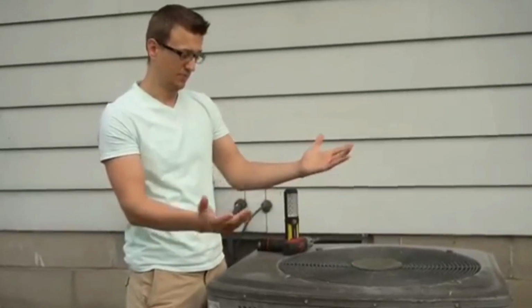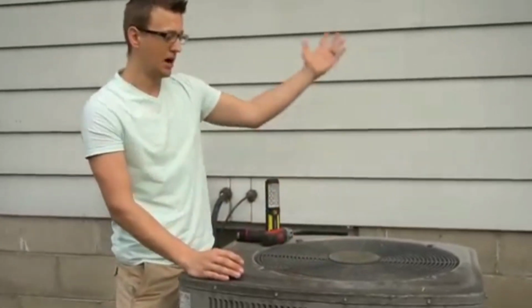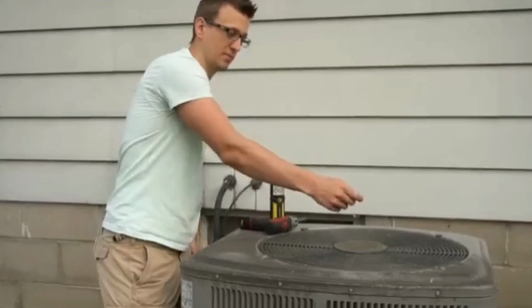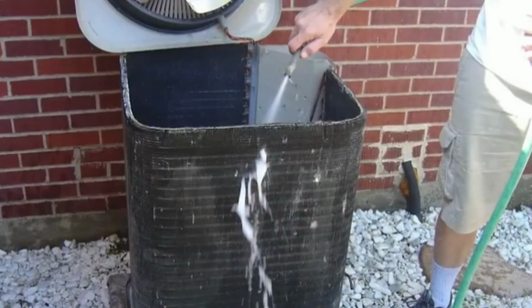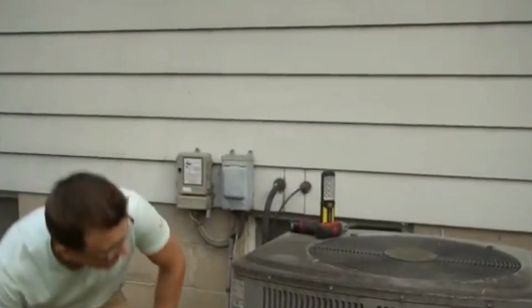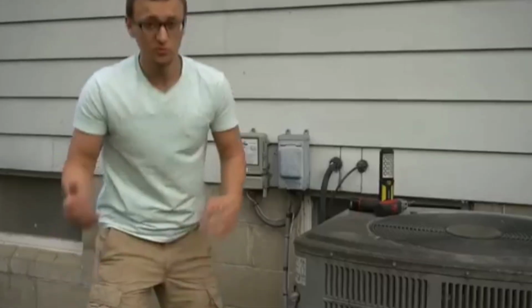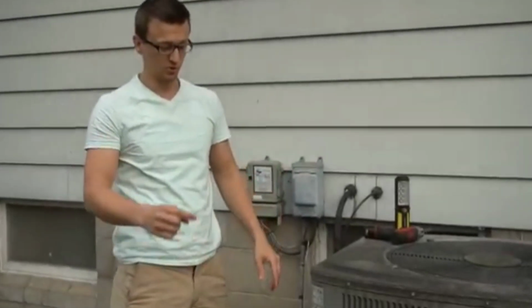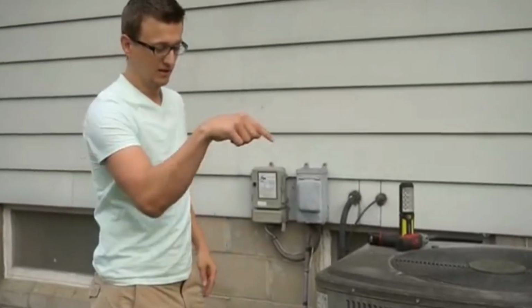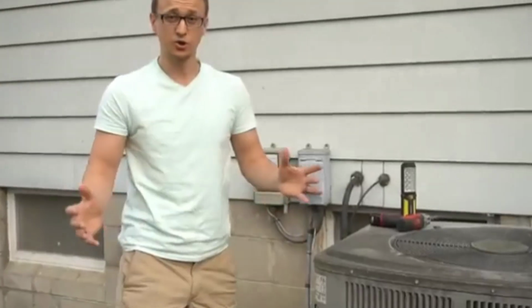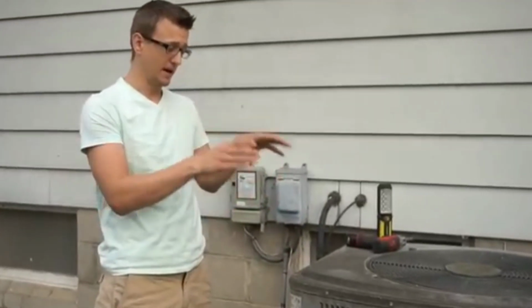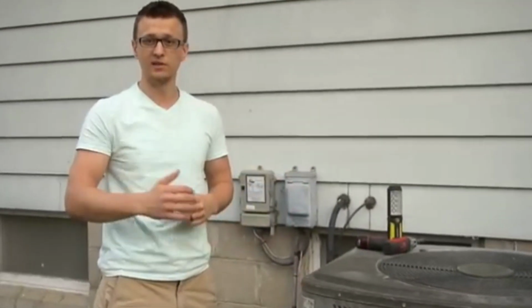The best preferred method is to take the top off of your unit and spray from inside out. I usually spray it just from the outside in, and that tends to be sufficient. It's very clean. You can see all the gaps through it. So most of the time it's sufficient to just spray with the water from outside in. And I'll show you how to do it because I know that my unit is pretty dirty from the end of the last season.